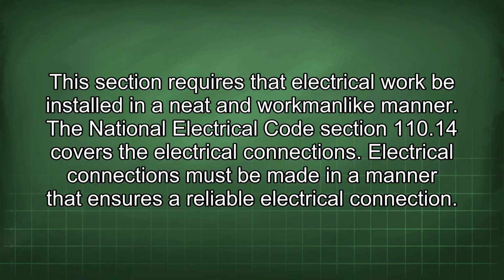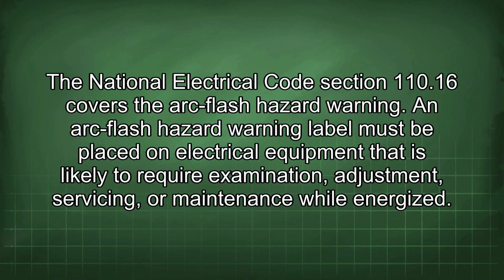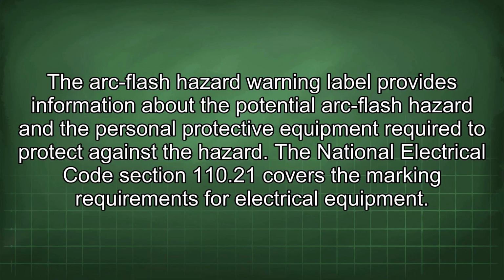The National Electrical Code Section 110.14 covers the electrical connections. Electrical connections must be made in a manner that ensures a reliable electrical connection. The National Electrical Code Section 110.16 covers the arc flash hazard warning. An arc flash hazard warning label must be placed on electrical equipment that is likely to require examination, adjustment, servicing, or maintenance while energized. The arc flash hazard warning label provides information about the potential arc flash hazard and the personal protective equipment required to protect against the hazard.